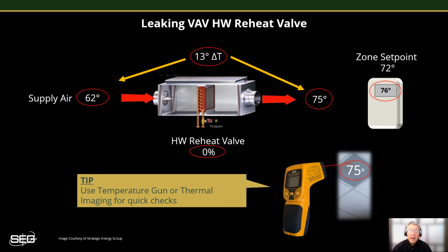The common handheld infrared temperature gun works well for quickly identifying issues like these. They also work great for surveying large areas, quickly scanning supply air grill temperatures, looking for supply grills that are substantially warmer than the surrounding ones. But just remember to override the reheat valves closed before scanning them to avoid confusion from any zones that might actually be calling for some heat.